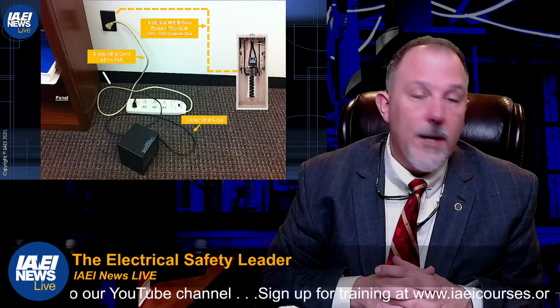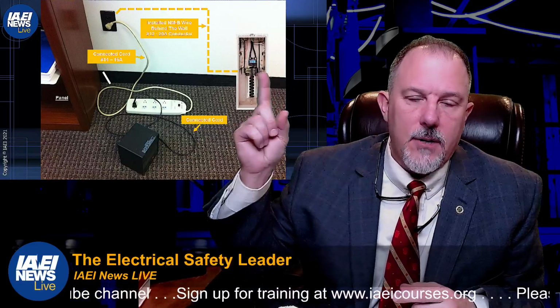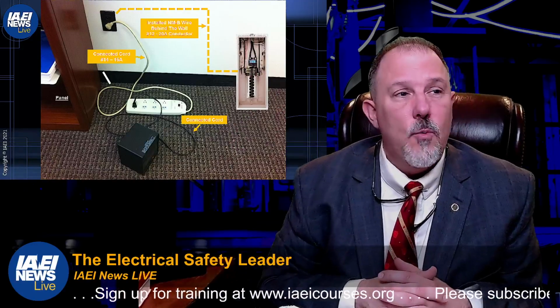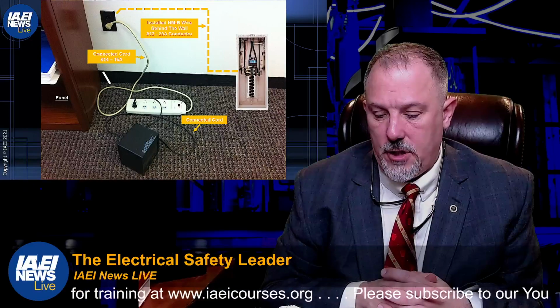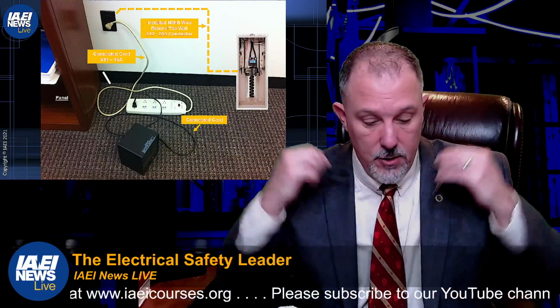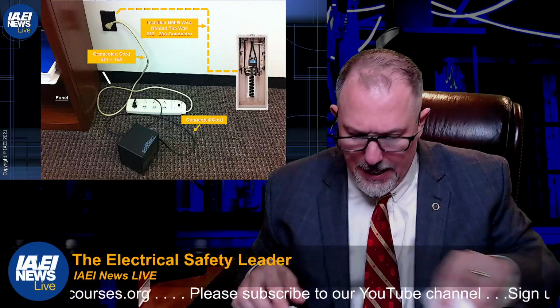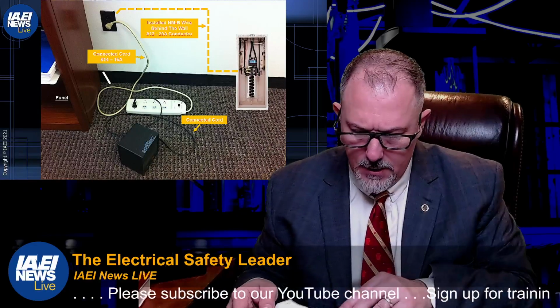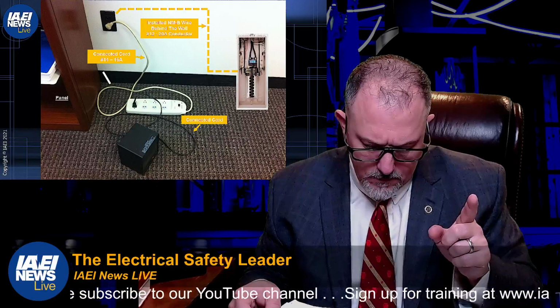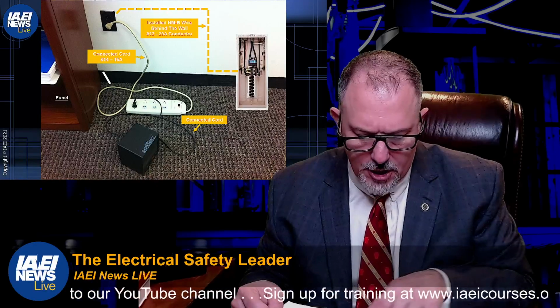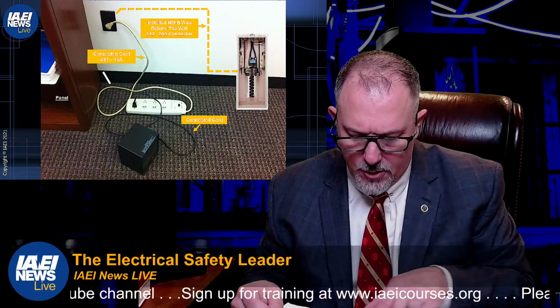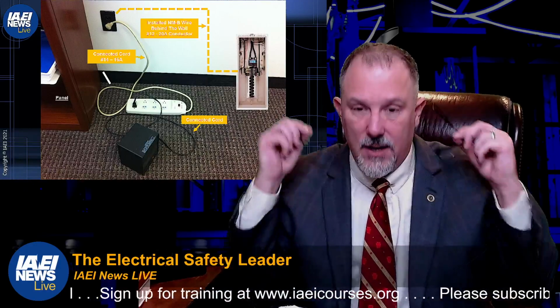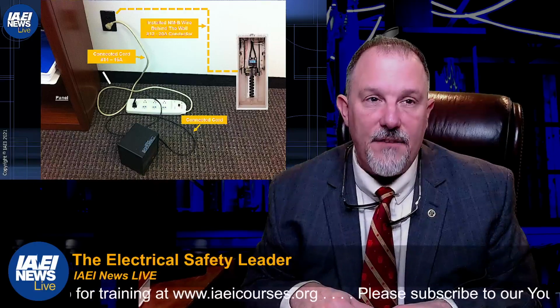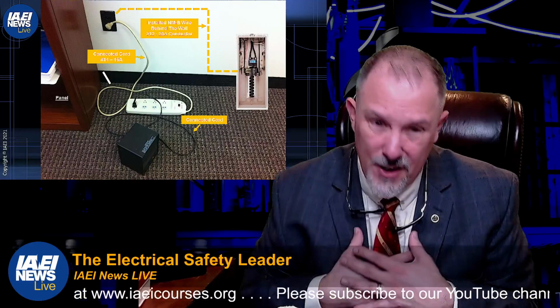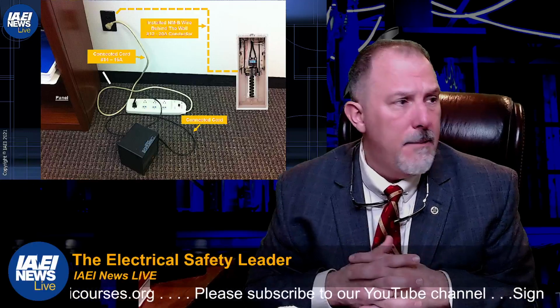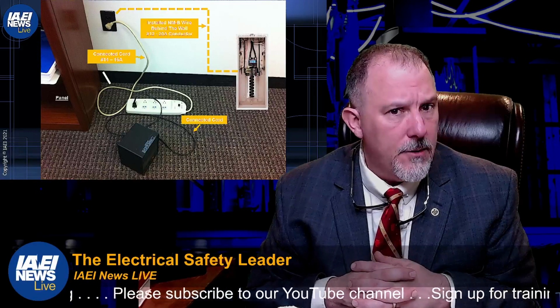So if you want shock protection, that breaker is not going to do it. You would have to do something different. When might I need shock protection? Crawl spaces, right? So crawl spaces, we added in 210.8, crawl spaces lighting outlets. GFCI protection shall be provided for lighting outlets not exceeding 120 volts installed in crawl spaces. Now you'll say, well, Tom, that doesn't protect the lighting fixture. It protects the human person from shock. I agree with that statement.